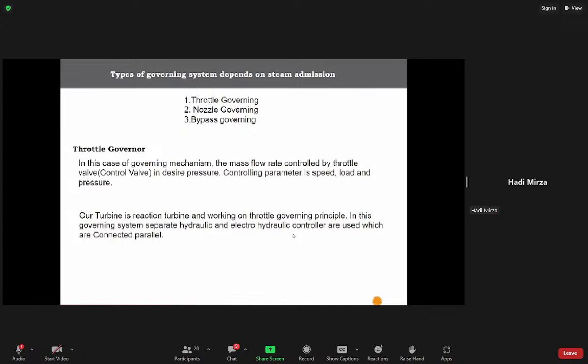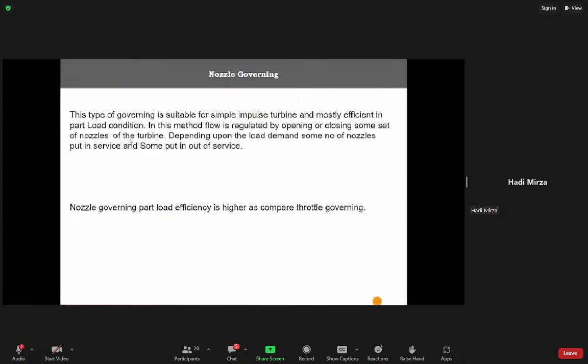Nozzle governing. Nozzle governing is basically used for low part load conditions. In this method, flow is regulated by opening and closing some set of nozzles of the turbine. Basically, in the TDBFP you can see this type of nozzle governing, in which 5 to 6 valves are there in the governing system. Depending on load, some of the nozzles are put in service and some are put out of service. When the load is around 350 megawatt, around 3 to 4 TDBFP valves will be in operation, and the remaining valves will be in closed condition.